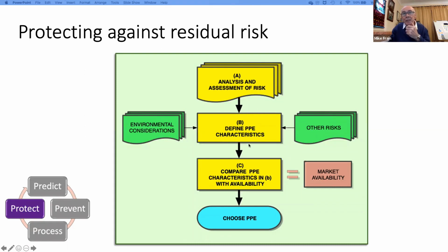But then it's about defining the PPE characteristics. And it's at that point we've got to think about how we do it, taking into account other risks and other environmental conditions. I work with a large IT manufacturer, for instance, where environmental conditions meant that they needed high order clean room protection, which was very, very difficult to obtain for arc flash at that time. And we had to work even harder on the prevent step, to make sure that we engineered out all the dangerous conditions in that particular site.